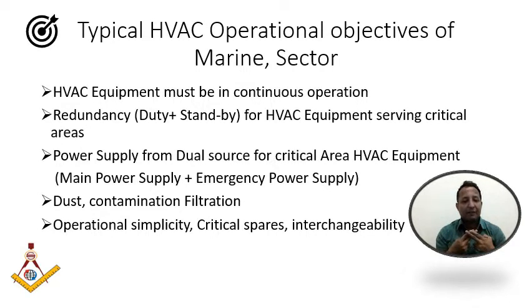Second is redundancy - redundancy of the HVAC equipment serving critical areas. The reason is that suppose something happens to the duty unit. Suppose only one fan is provided for the smoking zone, or only one fan for the kitchen - something happens to that fan, just imagine what will happen. The person will start feeling uncomfortable, pressurization will be lost, and there is always a danger of hazardous gases coming inside the accommodation. So for critical areas, redundancy is always a must.